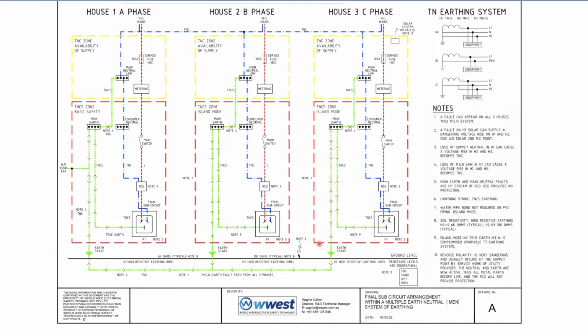Lightning strikes, look, that's note 6 there. If you had lightning striking the ground here, all 3 houses will get a voltage rise all the way up. And the biggest thing that I find with this is all your surge protection, all your lightning arresters and everything like that will only add to the damage. Once the power's coming up this way, as I can see the arrows going, the lightning strike happens here, and the power is running along all these things.